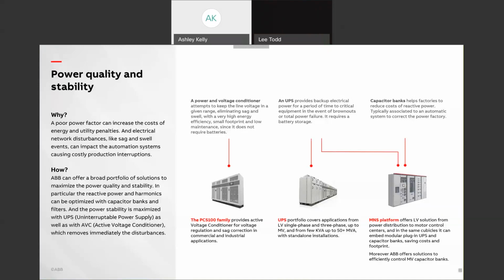A low power factor might be only one of the symptoms of a range of power quality problems that you're facing on your network. That can reduce both reliability and efficiency of your electrical equipment on your system. A full survey will detect any power quality issues such as harmonics, flicker, or unbalanced loads. We can then draw on our range of state-of-the-art equipment, including active filters, to provide you with the ideal cost-effective solution. And finally, we have power voltage conditioners.